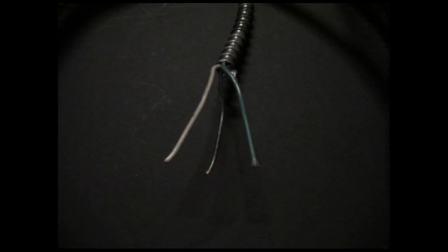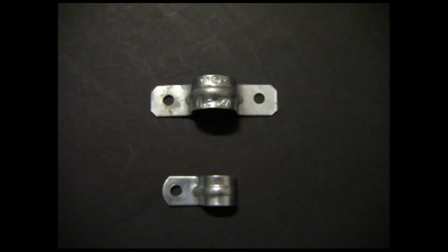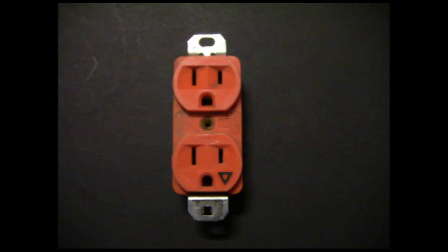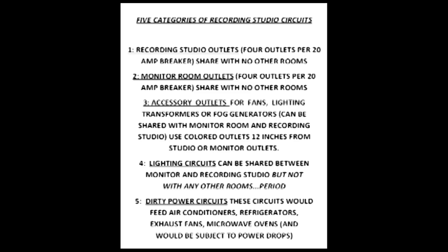12-2 MC is fully metal covered and shields against electromagnetic radiation, from here on out referred to as EMR. You want to divide your circuits into five categories. First would be the actual recording studio outlets. Second would be the monitor room outlets. Third would be accessory outlets — for things like fans, fog generators, or lighting that uses a step-up or step-down transformer. Use colored outlets for accessory circuits so you don't accidentally use them for musical equipment. Number four would be lighting circuits, which can be shared between the monitor room and recording studio, but never shared with any other room.